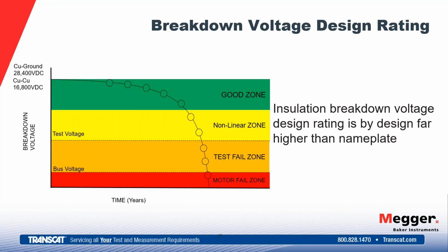And in this case, we're performing that test at a much lower energy level than every time you hit the stop and start button of the motor. Consider this: every time you're starting that motor, you're doing a high pot and surge on that motor with all the energy of the distribution system behind it. Here we're doing it at a very low current, very low energy level. And so if the winding is degraded, if we have a weak insulation, it can be destructive. But if the winding is not degraded, the answer is no. No significant degradation to that winding by high pot testing.